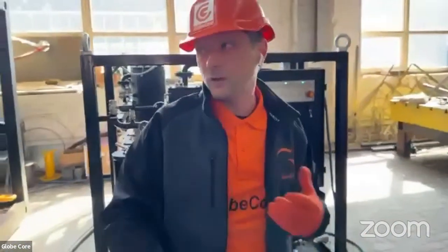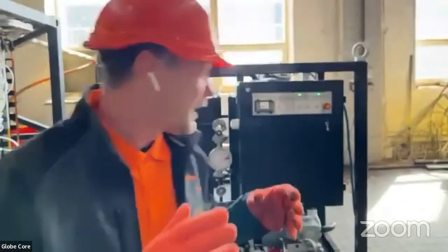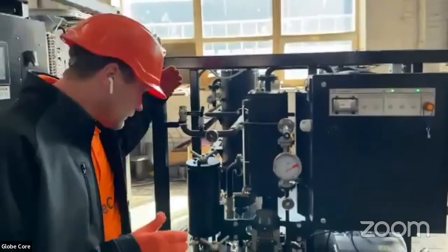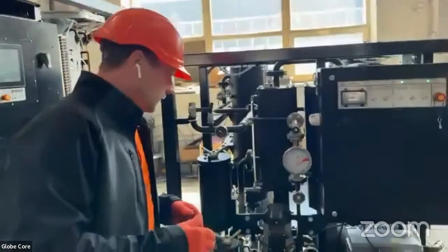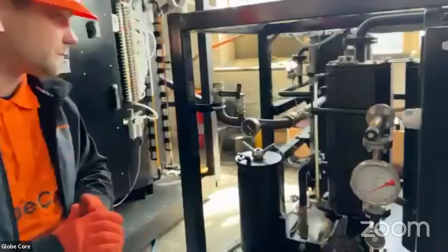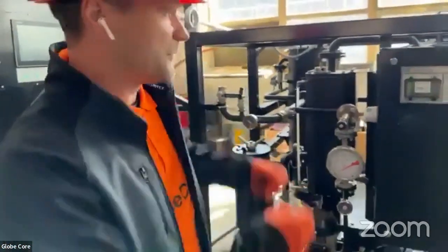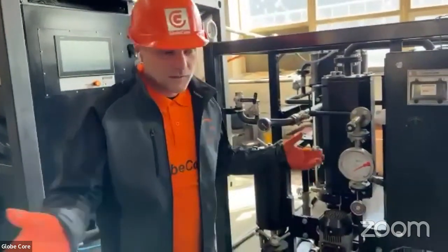They work for 60 to 80 minutes, and this is enough to provide the initial ignition of the sorbent. After that, the heating elements go off, and the burning process goes by itself. So we just supply air by the vacuum pump. Again, the reactivation is quite simple. Ignite it first, then we apply air.